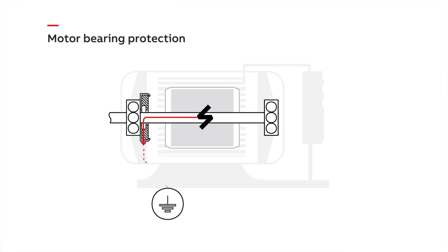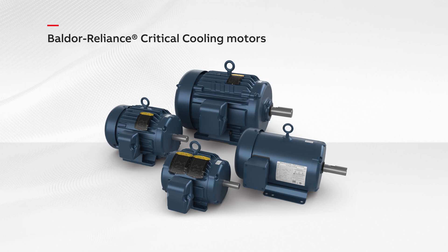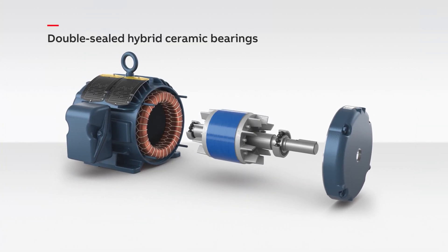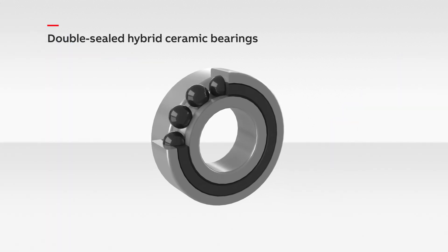These components are wear items and will become less effective over time. ABB offers an unprecedented lifetime warranty on motor bearings against shaft current in our Baldor-Reliance critical cooling motors. We promise your bearings will not fail due to common mode voltage. Our critical cooling motors utilize double-sealed hybrid ceramic bearings on both ends of the motor. These components prevent bearing damage caused by shaft currents because they are non-conductive — it's a foolproof method of protecting your motor bearings from shaft current failures.